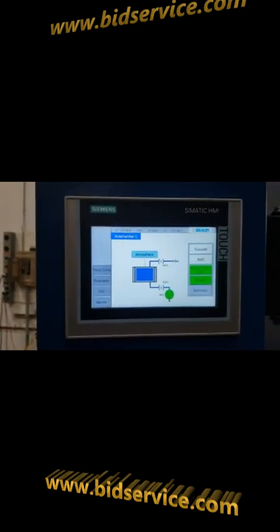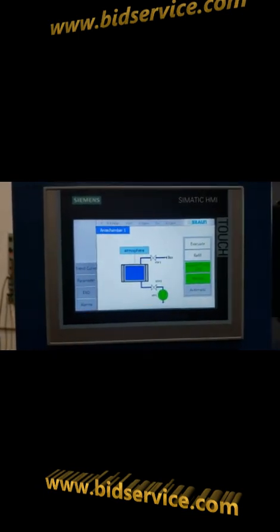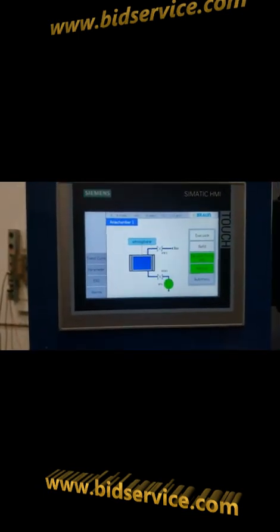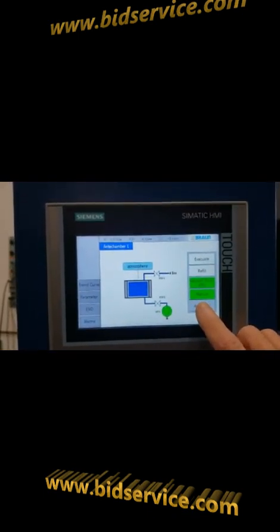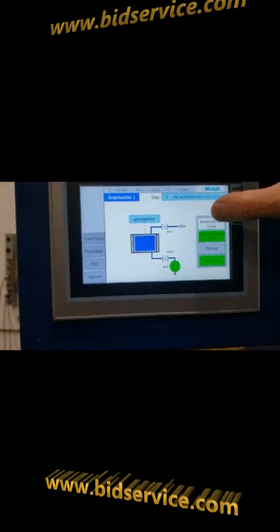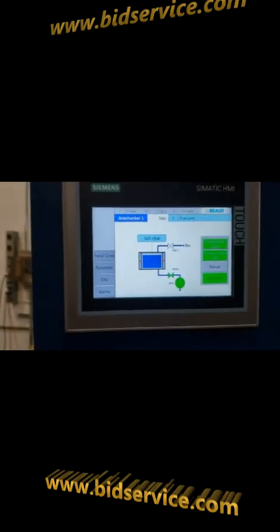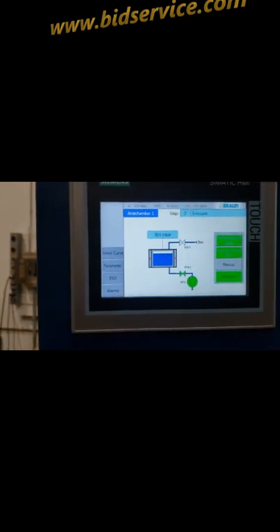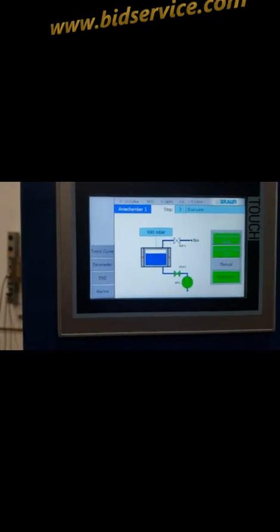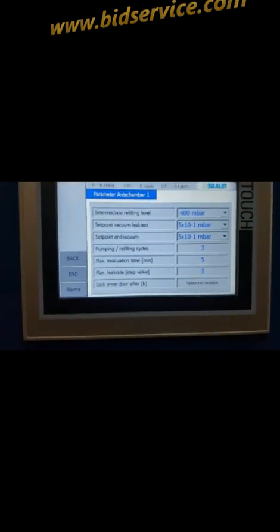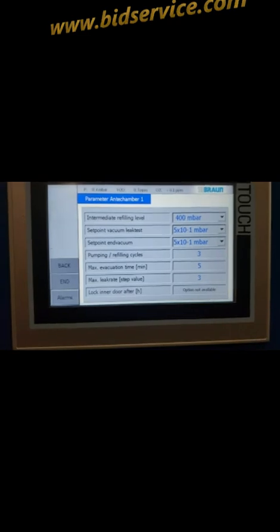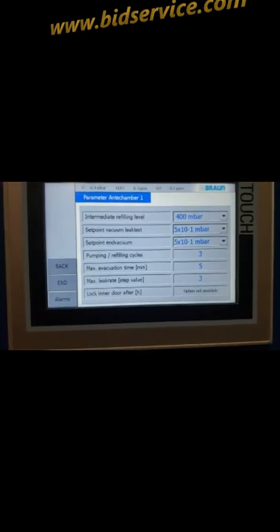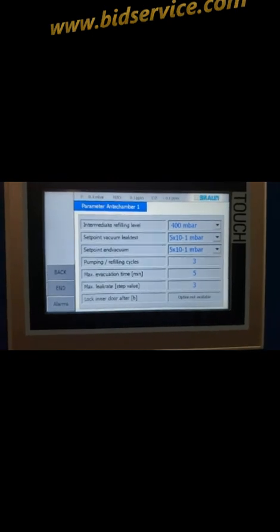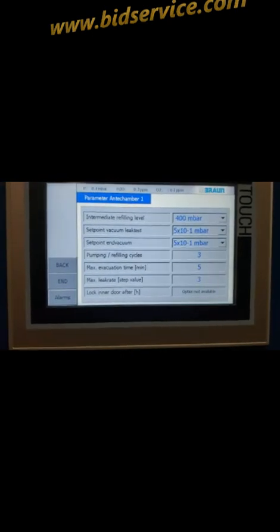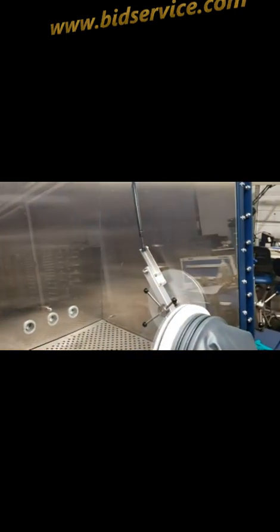Okay, so what I did here is I vented the antechamber to atmosphere in manual mode, and what I want to do is demonstrate the automatic mode. We'll hit the automatic mode button and then the antechamber cycle. This is going to run the program that is set in parameters, which will evacuate to 5 times 10 to the minus 1 millibar, and then do an intermediate refill to 400 millibar. It'll do that 3 times and then bring it back to atmosphere, so that you can open the inner door and bring your work in.